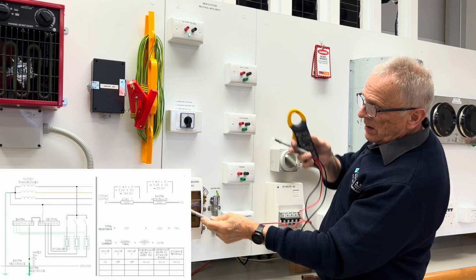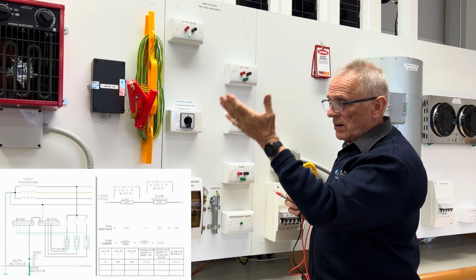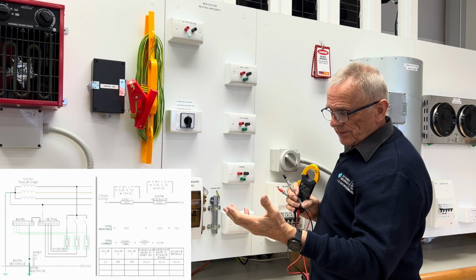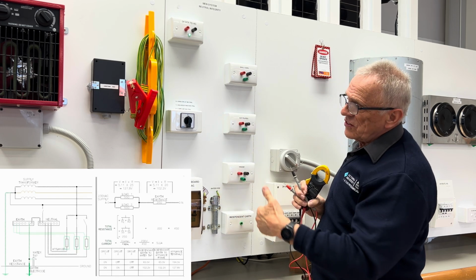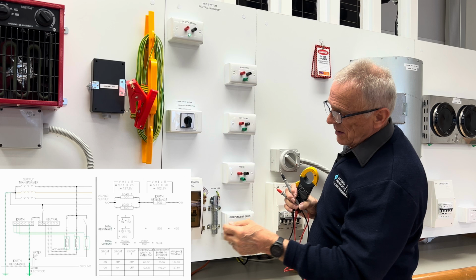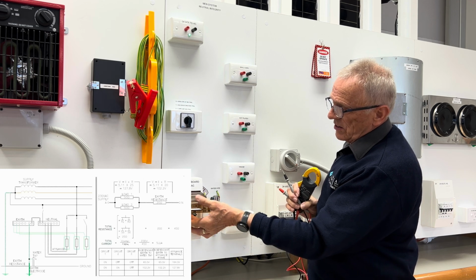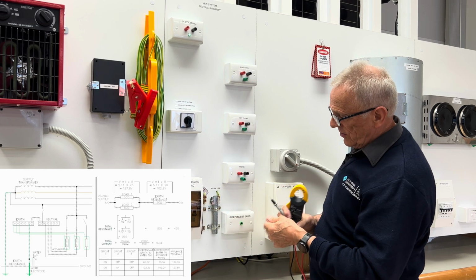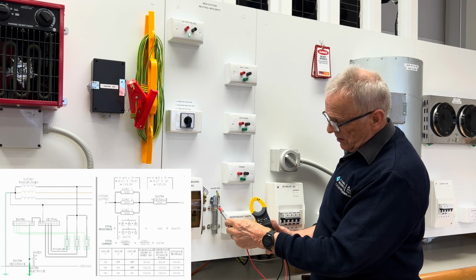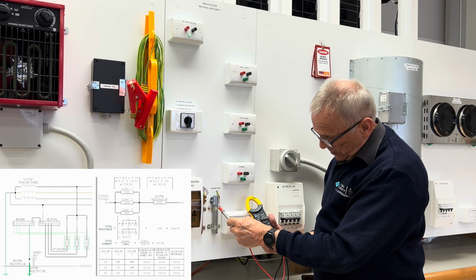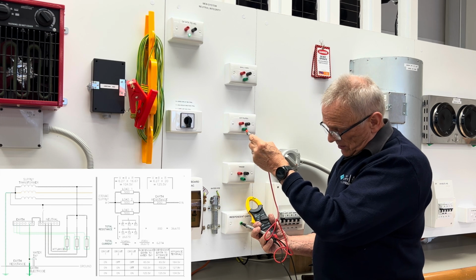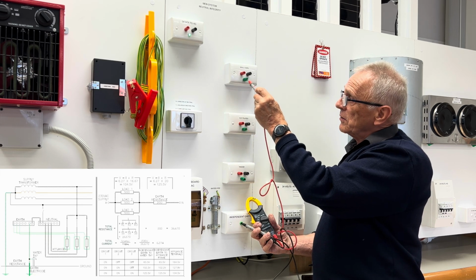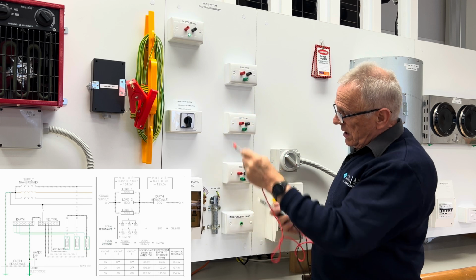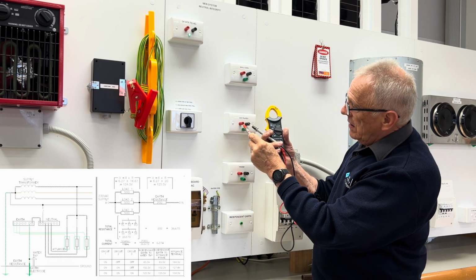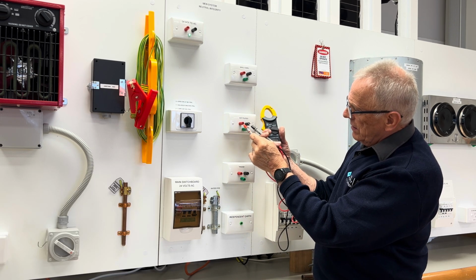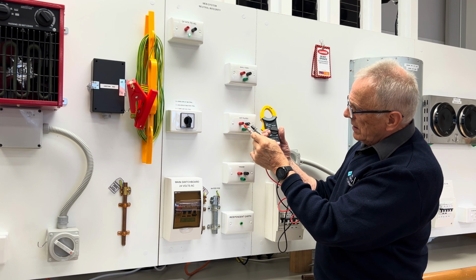Now, this is only one load. As we put more load on, we're going to increase the voltage on the earthing system, decrease across the load, becoming much more dangerous. So put more load on, you'll see now the voltage on the earthing system is up to 11.7 volts to the frame, wall oven and hot plate. And now you'll see across the load we have 12.13 volts, 13 volts.